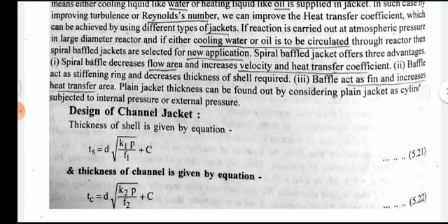Before that, let's recall that spiral baffle jackets offer three advantages. The first is that it decreases the flow area, so the velocity increases and the heat transfer coefficient increases. Second, the baffle acts as a fin and increases the heat transfer area. Third, the baffles also act as a stiffening ring, which supports the jacket.